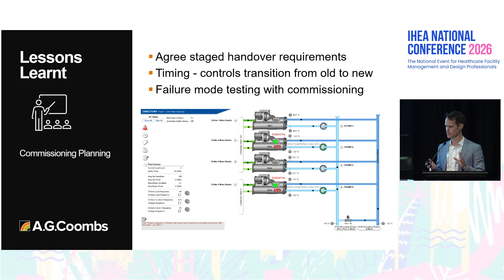We all spent a day on site putting the new chiller through any potential scenario we could think of, making sure it was staging properly and could accommodate fluctuations in condenser water temperature, playing around with decoupler flows, and importantly going through failure mode testing—isolating pumps, pulling out sensors, shutting off power to various things—to make sure the next chiller staged on and we got an alert or alarm. I can't overstate the importance of that process.